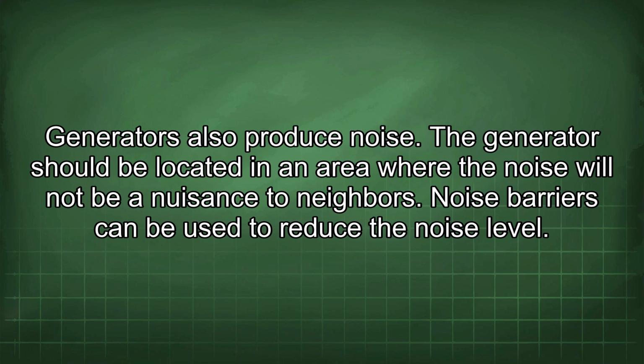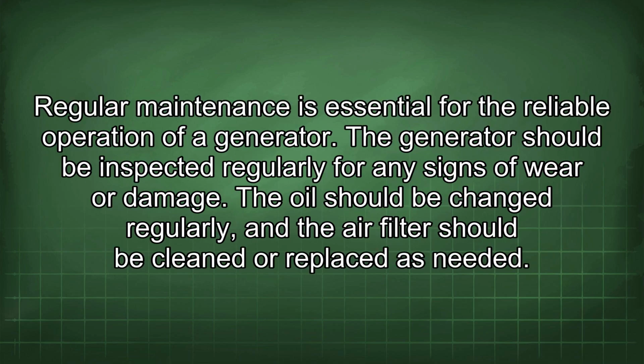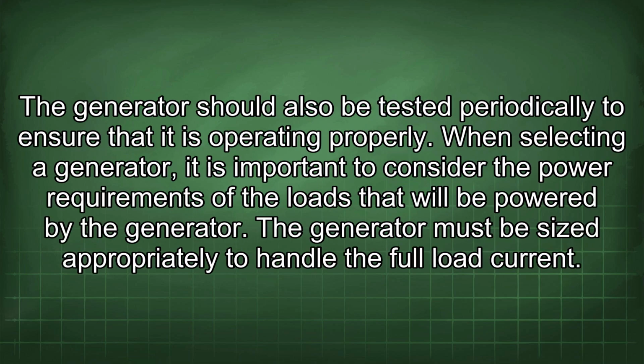Generators also produce noise. The generator should be located in an area where the noise will not be a nuisance to neighbors. Noise barriers can be used to reduce the noise level. Regular maintenance is essential for the reliable operation of a generator. The generator should be inspected regularly for any signs of wear or damage. The oil should be changed regularly, and the air filter should be cleaned or replaced as needed. The generator should also be tested periodically to ensure that it is operating properly.